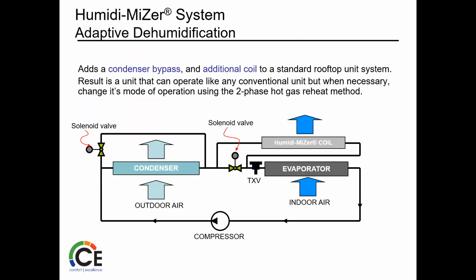The Humidi-MiZer option is out there, and it combines the older MoistureMiZer methods and the two-phase hot gas reheat system. So now we have kind of a combination going on. The Humidi-MiZer coil is the reheat coil, and it reheats the indoor air to a neutral temperature after the moisture has been removed. The condenser also has an added hot gas bypass line to bypass hot gas around the condenser. So now the Humidi-MiZer is a combination of what we've learned, what we see, what works better. We've got some refrigerant flow, we've got some metering, and we're going to roll on.